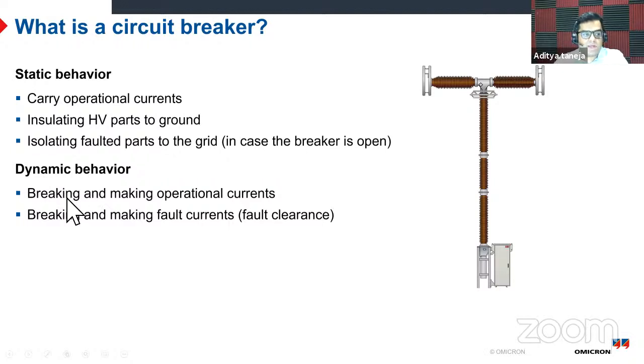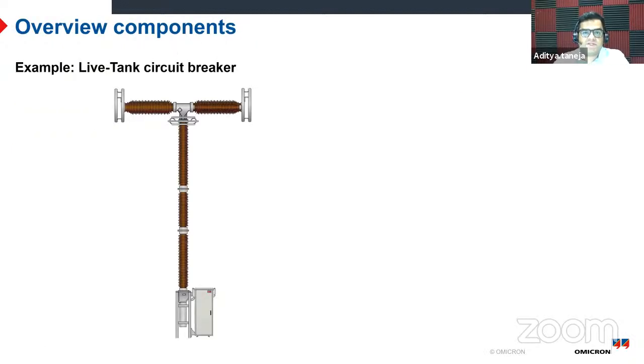And dynamic behavior is while it is operating, from open to close and from close to open. It should make and break operating current safely, and make and break fault current safely. This is a very good way for an engineer to look at a circuit breaker, as equipment able to perform these two behaviors. With this, I can now make a very functional, representative model of a breaker, in which I say that this is a 2-break-per-phase SF6 live tank design breaker with spring mechanism. But I can use this particular model to create a generic model which I can use to classify other breakers also.